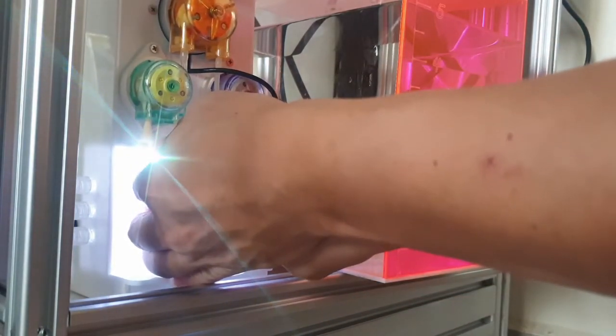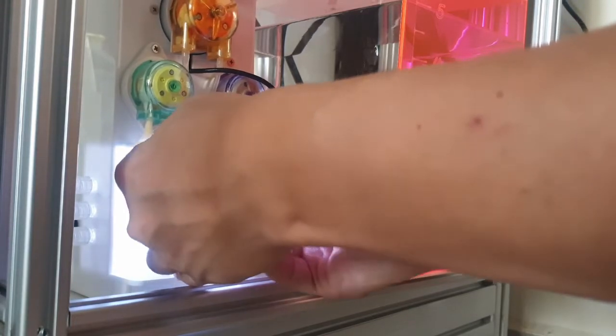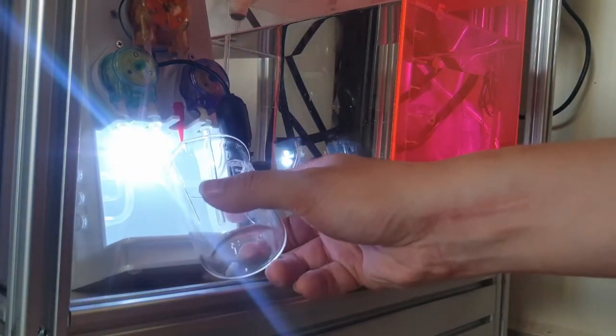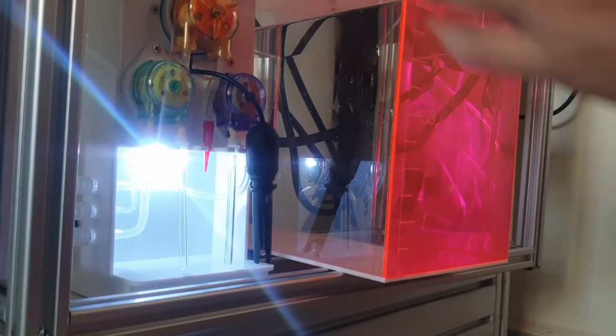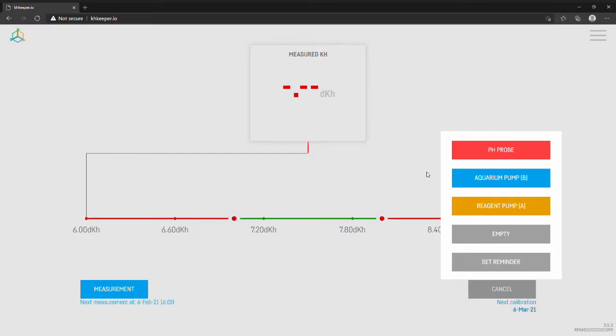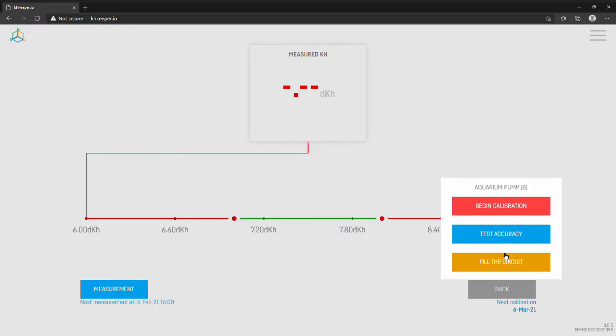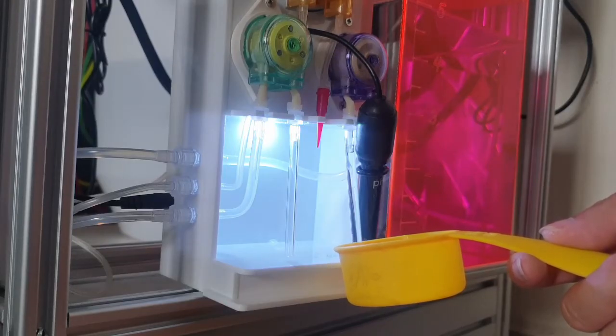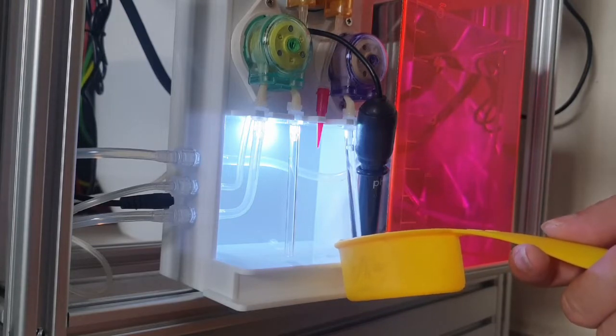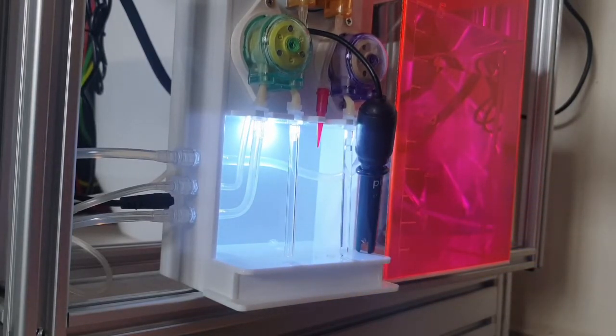So what I did was a slow push out of the dosing hose holder that is on the main body. I pushed out both of the hoses that are inside the beaker and slowly slid it out. And now back to our internet browser, we begin to fill the hose, and at this point make sure that there are no bubbles within all our hoses. If needed, just do a gentle tap to make sure the bubbles escape from the hose. That will ensure pretty accurate readings.